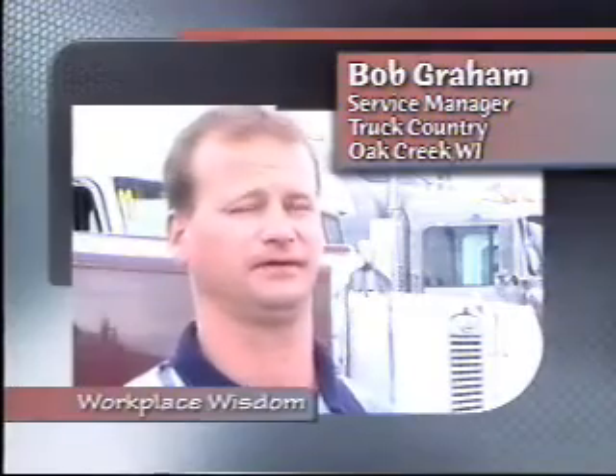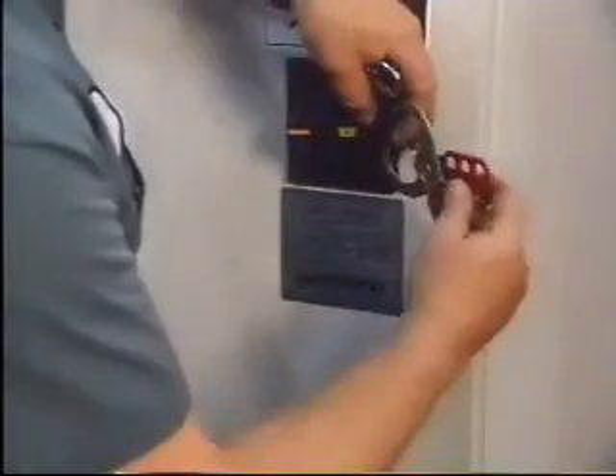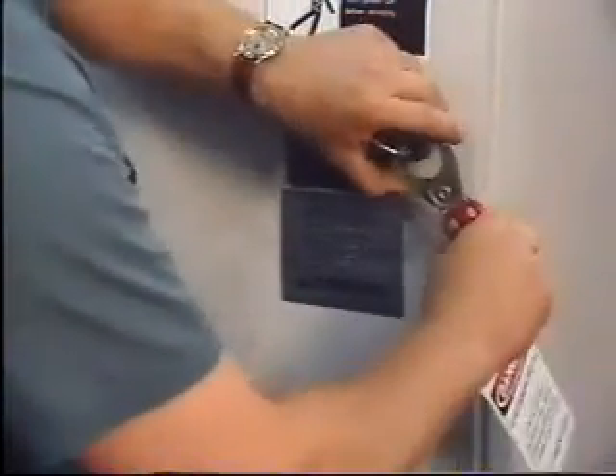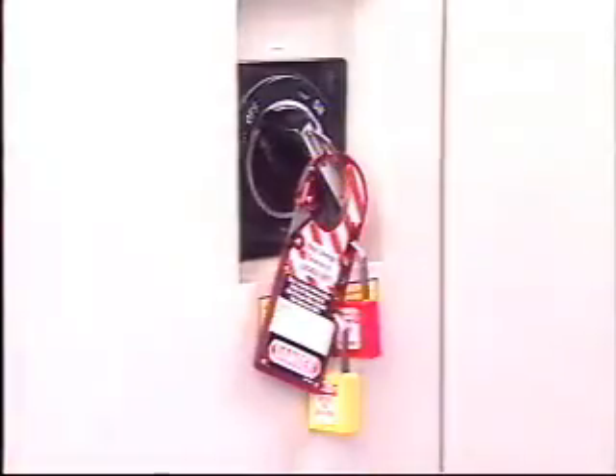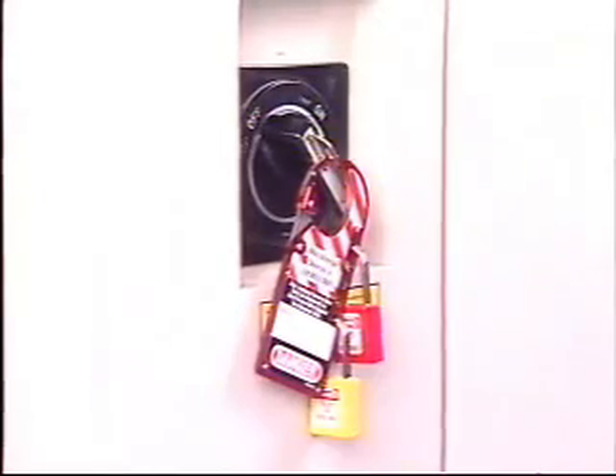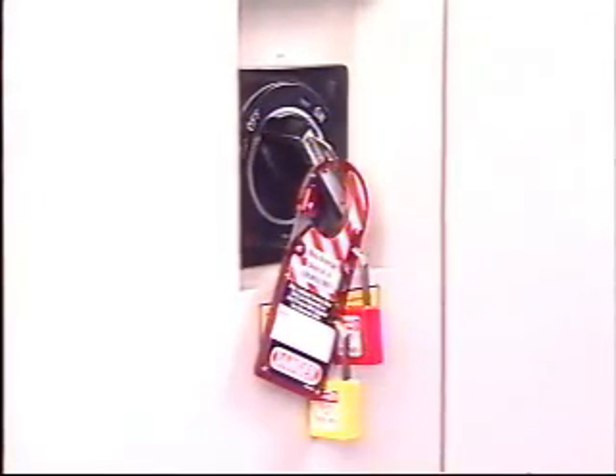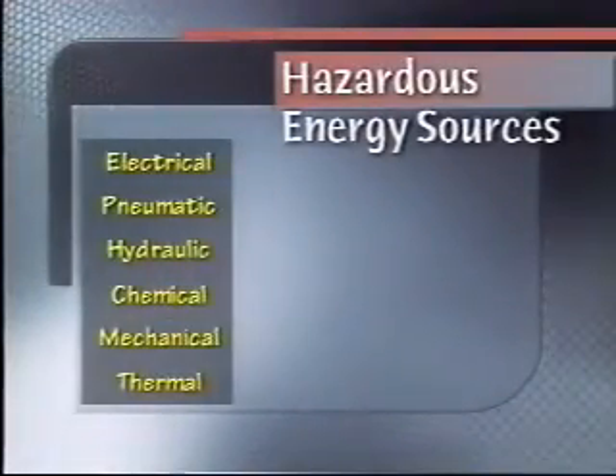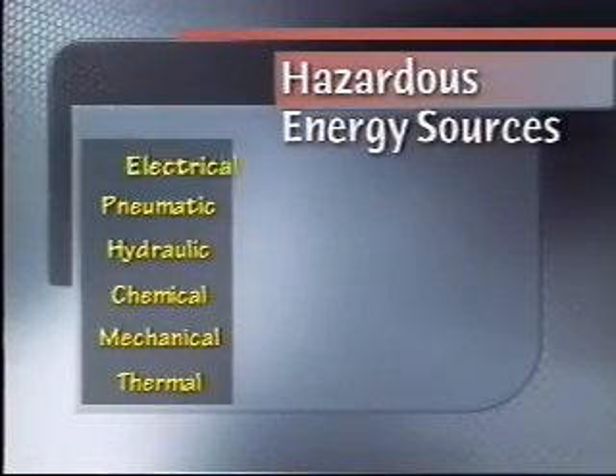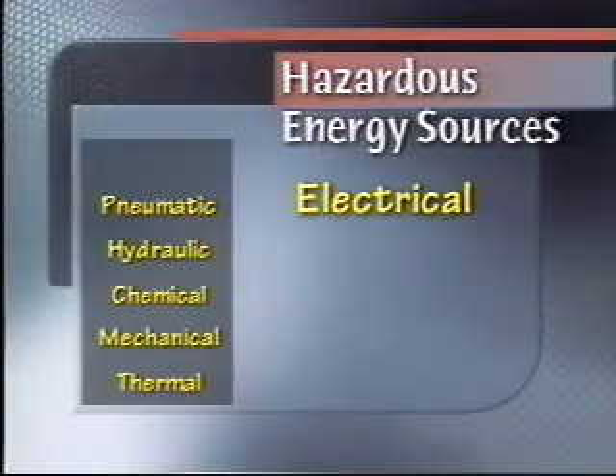Everybody in the facility needs to know about it. If the maintenance people or a technician are not available, they need to know what to do and who to contact, in order to keep people from getting hurt. The LockOutTagOut standard requires that before any maintenance or servicing work begins, hazardous energy sources must be blocked or shut off and isolated. When we say hazardous energy source, the first thing that comes to mind for most people is electricity, and for good reason.